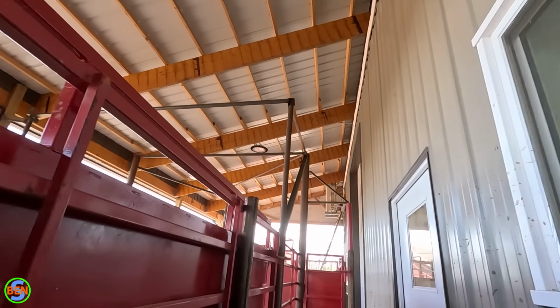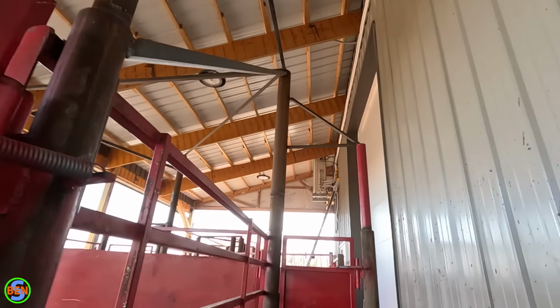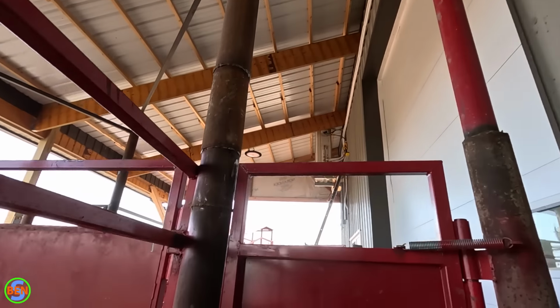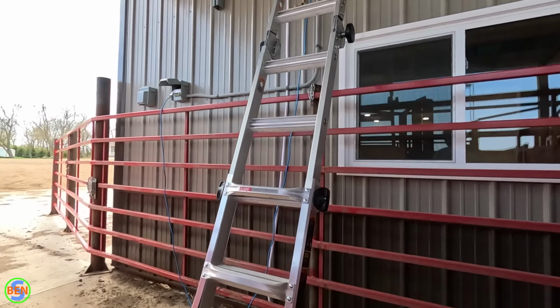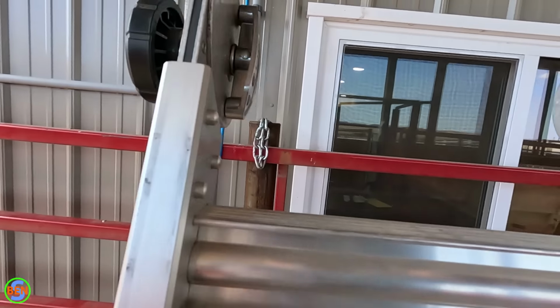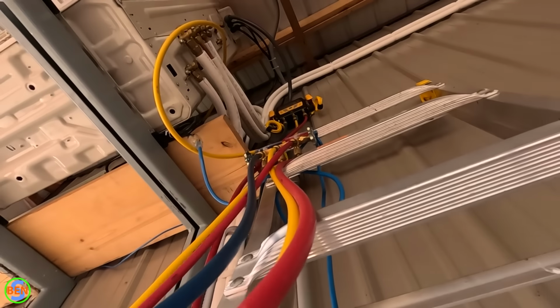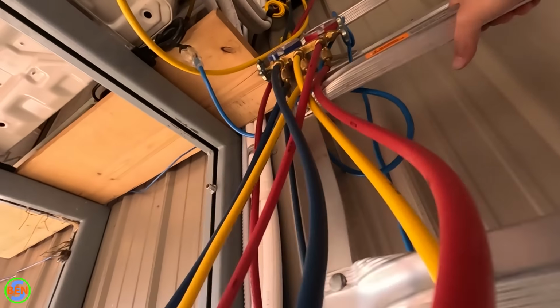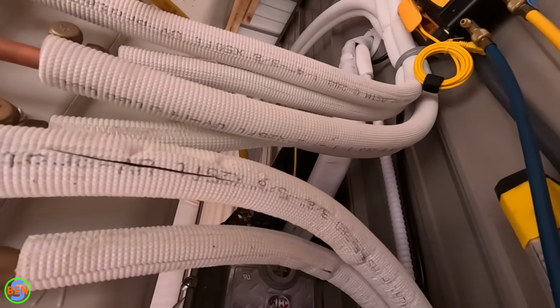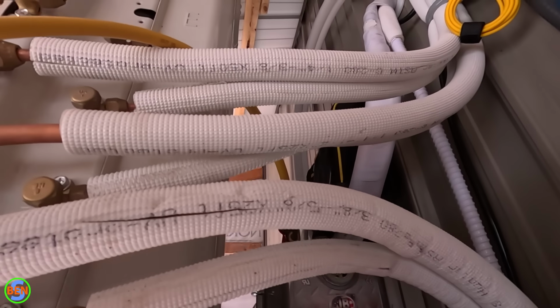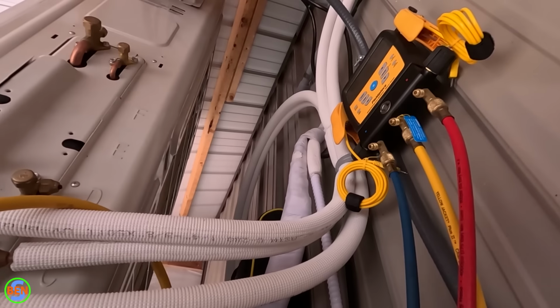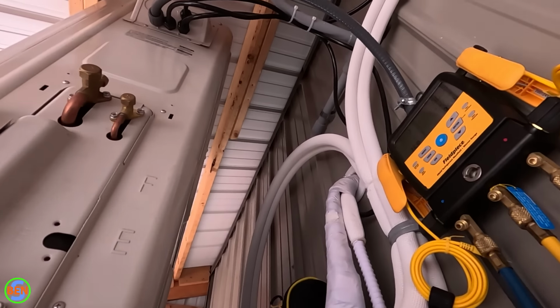By doing that, you are able to absorb the moisture out of the system and get that micron level to drop lower. Now, in my opinion, if you get it pulled down below 500 microns and it creeps back up to like 700 and something, that is fine. I have had no issues with that, and getting it to be below 500 microns and hold that for 15 minutes is very difficult. And you can comment down below if you're a fellow HVAC person, if you're always able to pull your vacuums down to 400 microns and they hold there for days on end, then that's incredible, and I want to know your secrets.